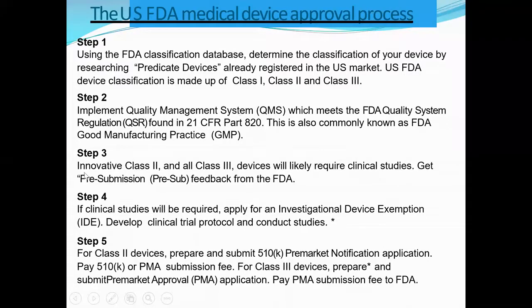The third process is innovative. Class 2 and all class 3 devices will likely require clinical studies. If your device is of low class, the low risk category, then you need not go for clinical evidence or clinical trials. But as you go to the higher and highest risk, that is class 2 and class 3, they obviously require clinical studies. So you have to get the pre-submission feedback from the FDA.